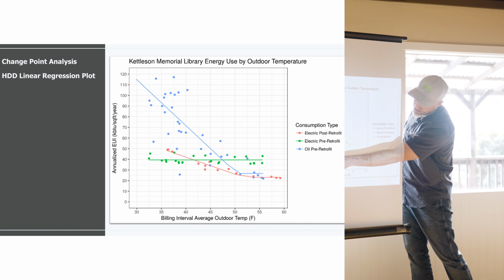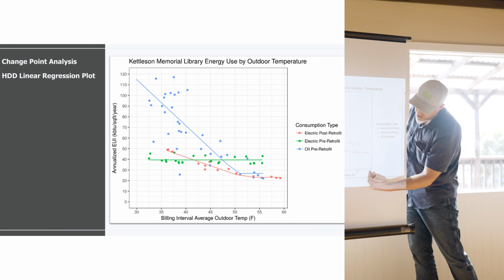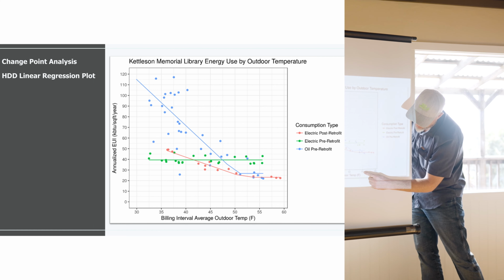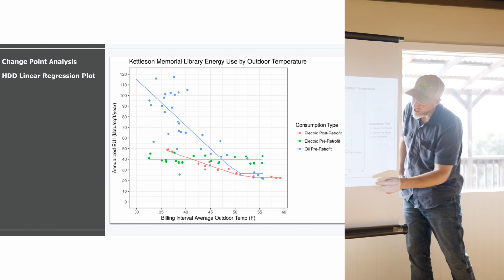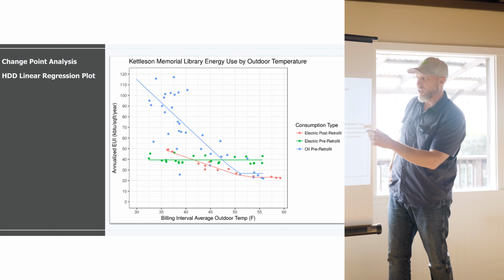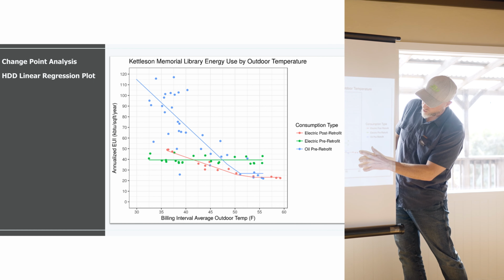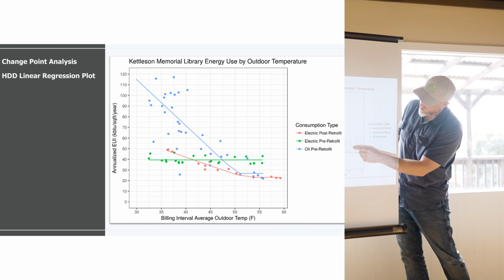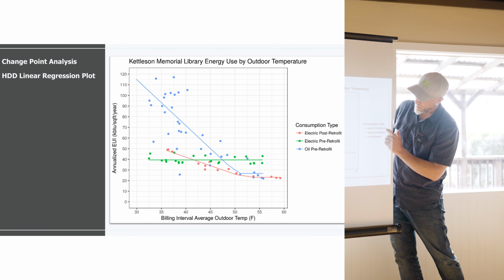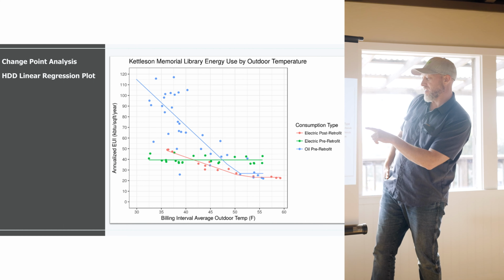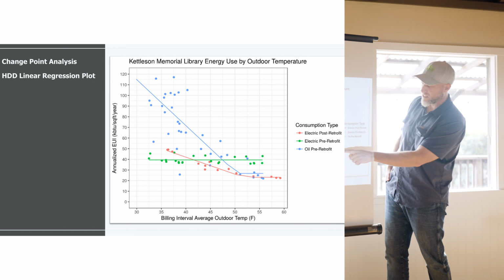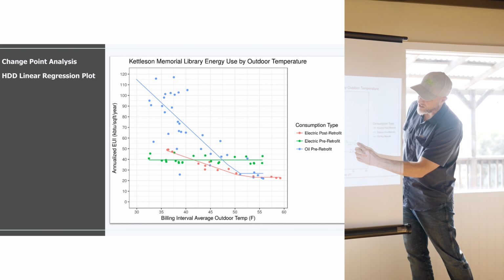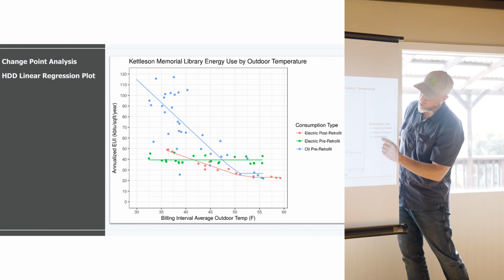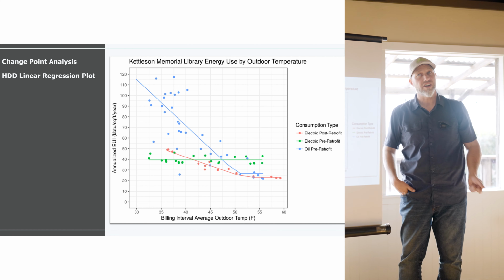On the vertical axis is EUI, annualized. On the horizontal is outdoor temperature: 55, 50, 45, 40. Change point analysis is really about when it changes, and the way it works there are three lines: the red is the electric post-retrofit, the after; the green is the electric before; and the blue was the oil, from an oil-fired boiler.